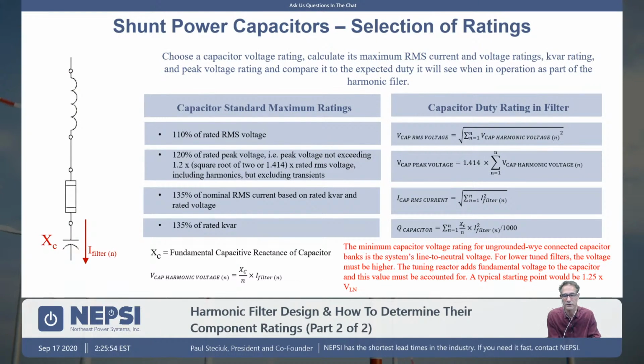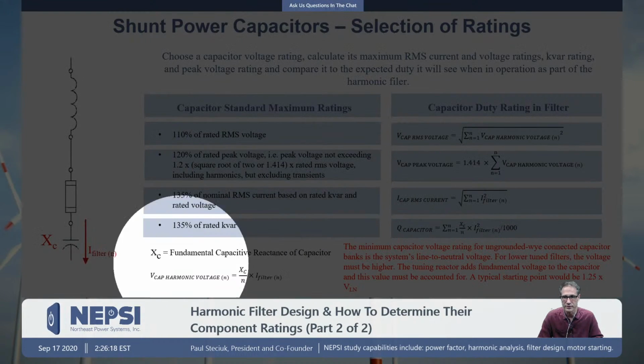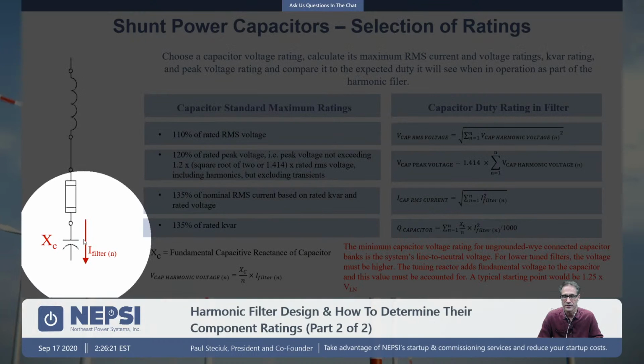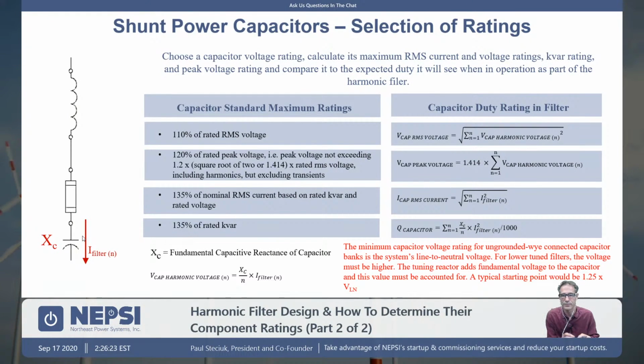So we can easily calculate the capacitor voltage based upon the harmonic current flow that would flow through that filter, based upon a harmonic study. Remember, you want to add margin to your design, so you want to make the value higher. Typically, you want to add a significant amount of margin. So from there, our philosophy is that you want to rate this capacitor so that the voltage during normal operation is no greater than basically 1 per unit, its rating.